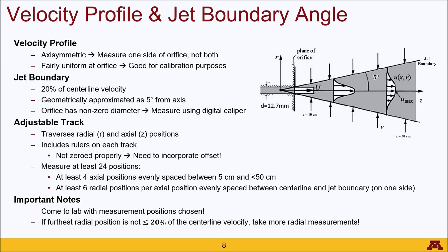The adjustable track allows you to traverse both radial and axial positions, and on each track there is a ruler to keep track of your measurement position. However, each ruler is not zeroed properly. The zero point on the z-axis will be set at a distance away from the orifice, and the radial position corresponds very poorly to the ruler on the radial axis. You might find that the axis point is at something like 70 millimeters instead of zero, so you need to incorporate those offsets.